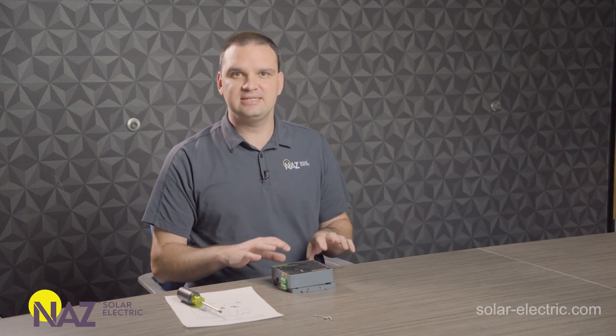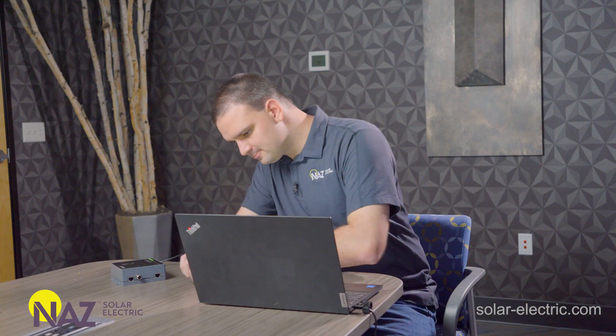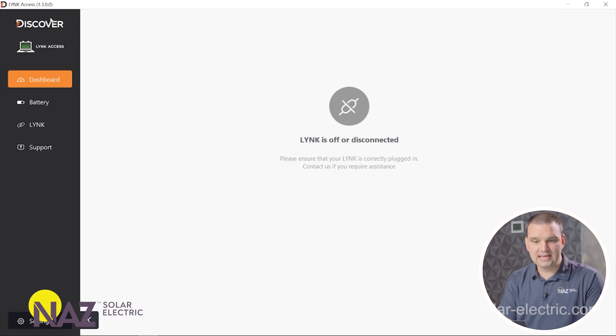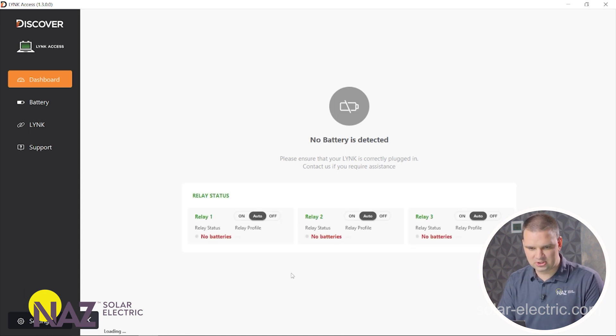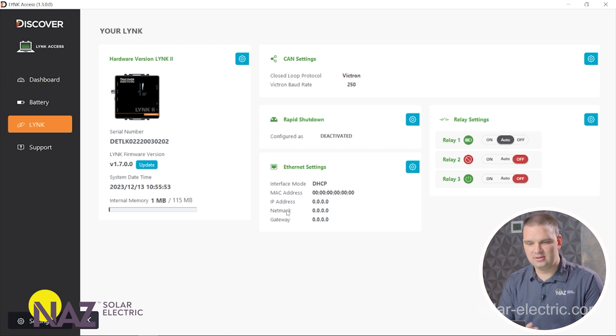Then we can go to the laptop, connect it, and software-wise, program it for Victron. Now that we've opened up the LYNK II and changed the pins to reflect the inverter system we're working with, we're going to program it using LYNK Access on the computer. We'll connect it using the provided communication cable. In LYNK Access, we go to LYNK and see an overview of how the LYNK II is currently programmed. We can see what firmware the LYNK II is running — the latest version is 1.7, so we're up to date.